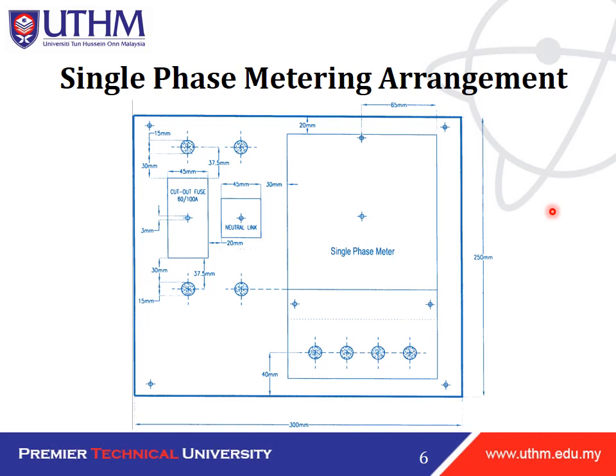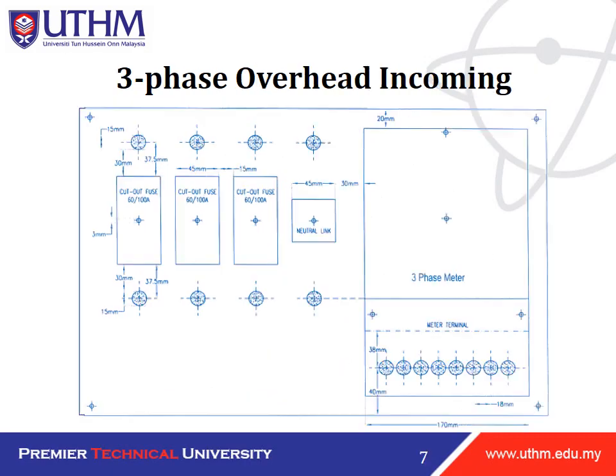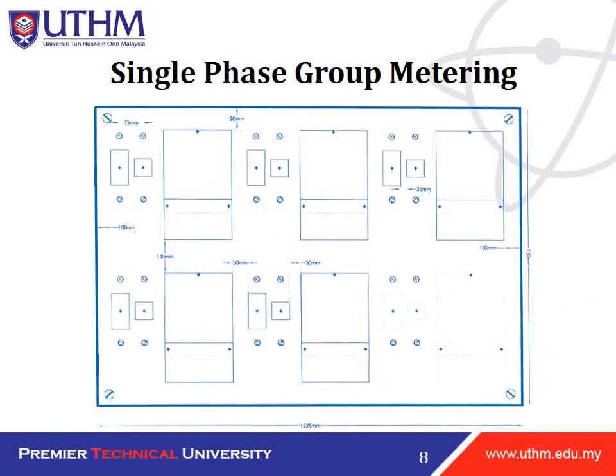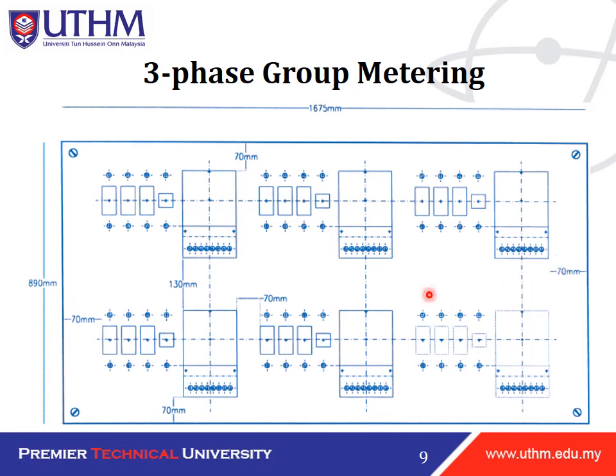Okay, this is the example of single phase metering arrangement in the DB board. So the single phase meter here represents the kilowatt hour meter. Okay, this is the three phase overhead incoming for three phase meter. So we can see the difference between the single phase and three phase from this diagram. This is the single phase group metering. We can see here we have 5 pieces of single phase metering. And then this is the three-phase group metering. We can see the three-phase metering is more complicated compared to the single phase just now.